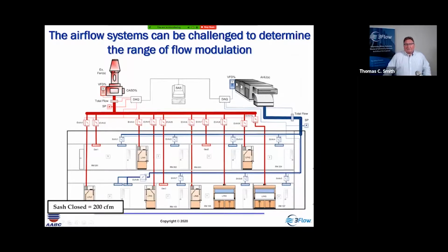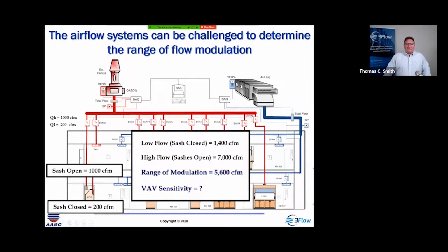We expect that when the sashes are closed, we've got 7 hoods on the system. 1, 2, 3, 4, 5, 6, 7. They're all connected to a manifold exhaust. The supply is working in conjunction. So sash closed, 200. We open the sash, we go to 1,000. The valve's programmed for 200 to 1,000. If we were to add that up from minimum to maximum for these hoods, we would see all sashes closed, 1,400. We open all sashes, 7,000. Our range of modulation would be 5,600 CFM.